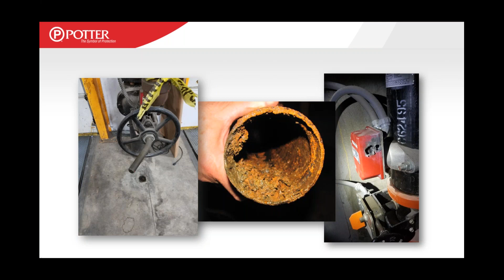And that's why the codes require and mandate that these systems be maintained in accordance with NFPA 25. These are a couple of pictures I just grabbed off of social media sites that some of you are undoubtedly on and pay attention to. But some of these issues happen suddenly, right? You see the bent stem on the OSY that could happen instantly with a forklift or a car, versus some things like corrosion that take a period of time. But we know that these are the kinds of things that drive that sprinkler system success rate down, and that's why the codes say it's important for us to be on the lookout for these kinds of problems.